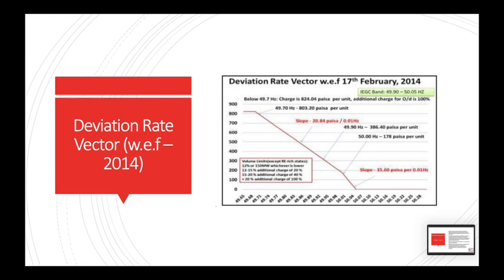Now it simply comes down to what my break-even frequency is, or my ECR rate. If my ECR rate is less than the DSM rate, I would definitely try to inject more at that particular frequency, and if my ECR rate is greater than the DSM payable rate, then I would try to inject less.